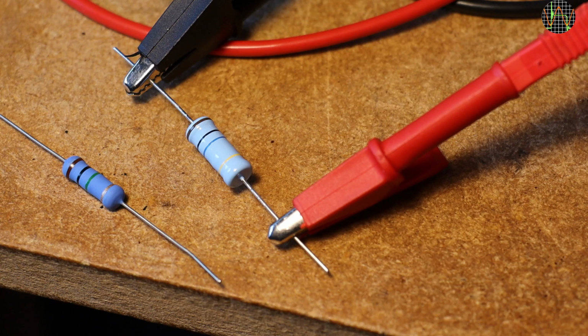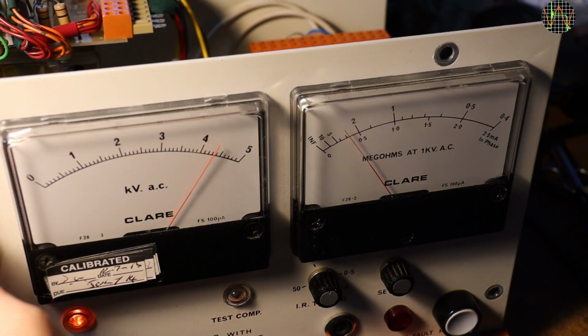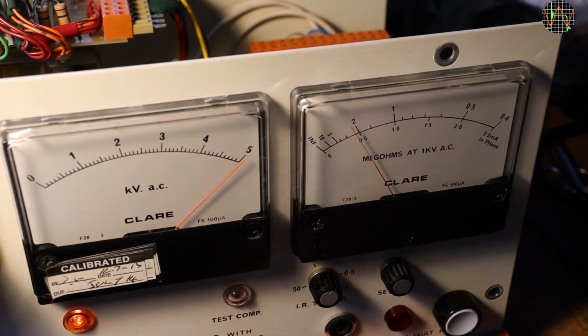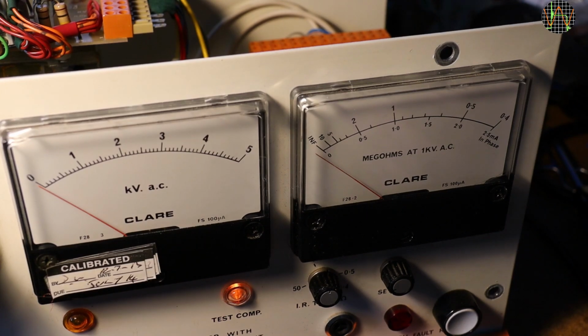The 10 megohm resistor reading only 2 megohm is because the megohm scale is only valid at 1 kilovolt, so at 5 kilovolts I should read 5 times less, or 2 megohm. This test loads the resistor with 2.5 watts, but this is a 3 watt type, so it should be okay. Okay, I need to up the voltage, but here we are, 5 kilovolts. The current approaches the 0.5 mark, but remains slightly below. When the timer finishes, it's clear that the null/inf point isn't set quite right, which explains it. Apparently, if you want precise measurements, you have to check and set this with the inf pot on the front plate every time when changing the output voltage.